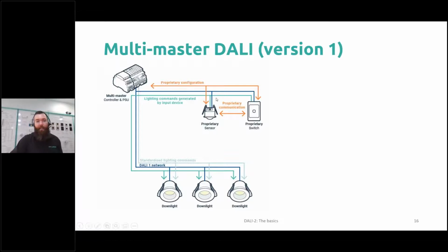And I'll give you an example of that now. So you can imagine in one of these systems, these sensors themselves were typically the ones actually sending the lighting command. If someone walked into that room, this sensor is going to detect it and say something like, lights in group 4 turn on. Okay, now that's great. If nobody moved in that particular room, the sensor would have some sort of timeout, and after about 15 minutes, we're going to get lights in group 4 dim down to a warning level. A few minutes later, lights in group 4 turn off.